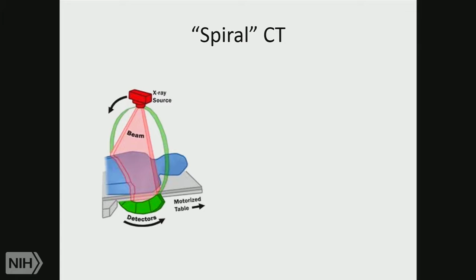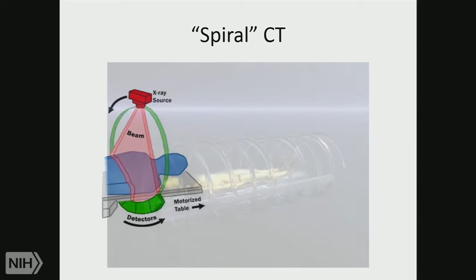Now, we talk about the spiral CT, and that's because the acquisition is occurring as the patient is moving on this table. And so in space, it prescribes a spiral around the patient. So the X-ray tube is moving, the patient is moving, so you get this kind of coil-like or spiral-like appearance. And that's important because we think about CT scans as these individual slices. That's what we look at. But that's not really what they are. They're really volumes of data. And then they're retrospectively cut in the way that we see them. So we obtain it as a volume, and then we cut it.